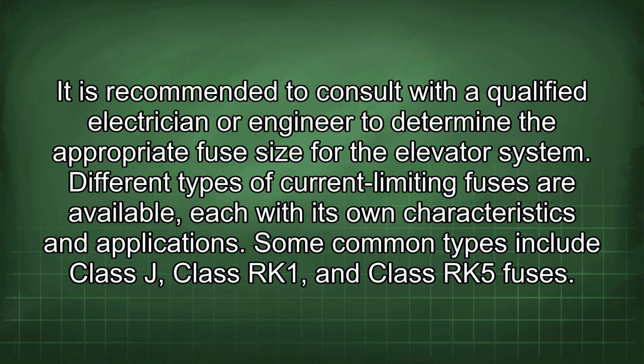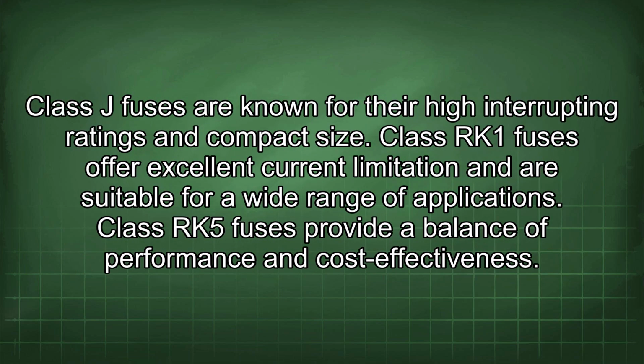Different types of current limiting fuses are available, each with its own characteristics and applications. Some common types include Class J, Class RK1, and Class R K5 fuses. Class J fuses are known for their high interrupting ratings and compact size. Class RK1 fuses offer excellent current limitation and are suitable for a wide range of applications. Class R K5 fuses provide a balance of performance and cost effectiveness.